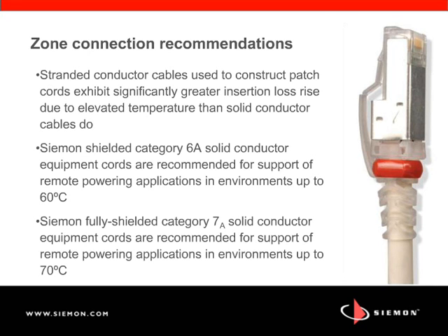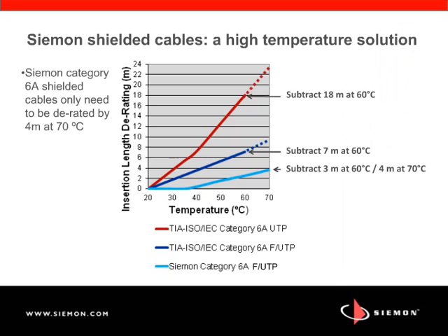I want to talk a little bit about products that are designed beyond the standard 60 degrees C operating range. I'm going to be looking at the Siemon Category 6A and 7 product line, but this type of analysis can be applied to any other vendor that has cables that are characterized for greater than 60 degrees C. The takeaway here is, the shielded cables exhibit extremely stable transmission performance at elevated temperatures, and they require less length reduction than specified by TIA and ISO to satisfy insertion loss requirements. This is important because it provides the cabling designer with significantly more flexibility to reach the largest number of work areas and devices in a converged cabling environment.